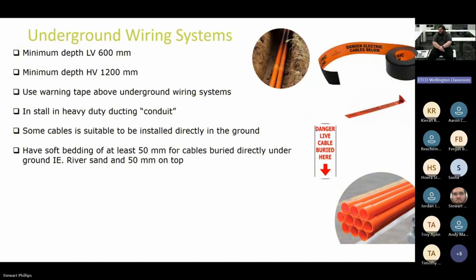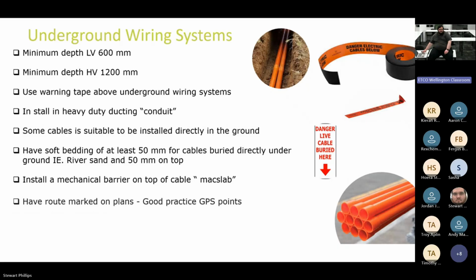Have soft bedding of at least 50 mil for cables buried directly underground, i.e. river sand, and 50 mil on top. So dig to 600, 50 mil of sand, chuck cable in, 50 mil of sand, compact, stone 100 mil, danger tape, fill trench. Install a mechanical barrier on top of cable called a MAC slab or mag slab. This will be dependent on the system that you are using.